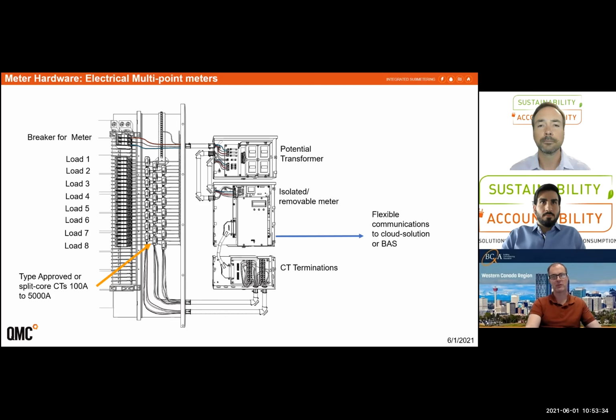If someone is seeking revenue grade, how often do they need to be looked at on a yearly basis, like from a calibration standpoint, or once they're Measurement Canada approved, they're good for life? Yeah, great question. So any Measurement Canada approved meter is given a seal period, and it's stated by Measurement Canada. So most electrical meters have a 10-year seal period. So once it's installed and commissioned, you just need to remove it every 10 years and retest it. And usually when you reinstall it, it's given a slightly longer seal period the second time around, like say 8 years. If you have a substantial amount of the same meter deployed, you can look at sample testing.